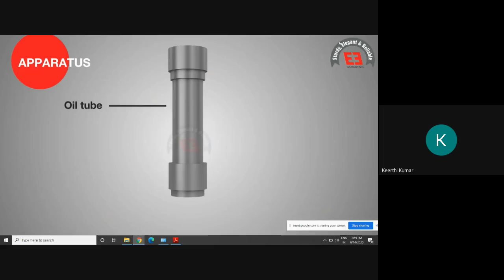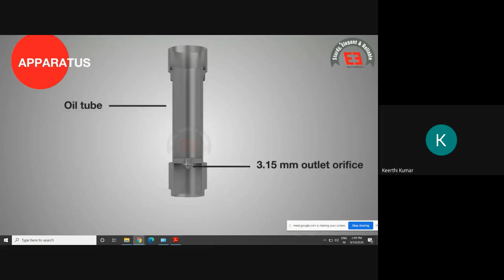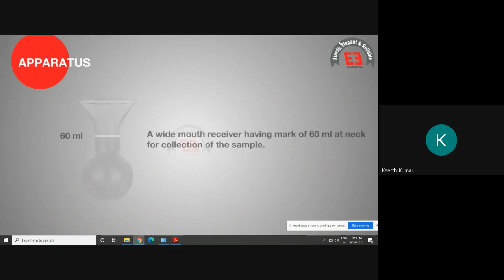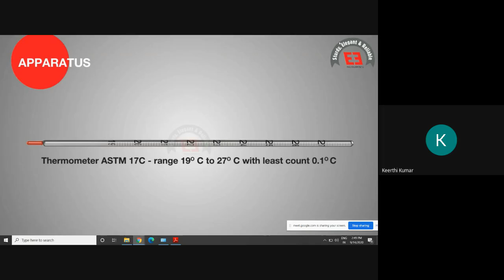Apparatus. Saybolt Furol test apparatus consists of an oil tube with overflow rim at the top. The oil tube is having an outlet orifice of 3.15 mm internal diameter and a stopper cork at the bottom. The oil tube is fixed in a thermostatically controlled water bath with stirring device. The lid of the water bath is having a heater and cooling coil to bring down the temperature of the bath media. The bath is placed on a tripod stand with leveling arrangements. A wide mouth receiver having a mark of 60 ml at the neck for collection of the sample. Thermometer ASTM 17C, range 19 degrees Celsius to 27 degrees Celsius with least count of 0.1 degrees Celsius. Thermometer ASTM 19C, range 49 degrees Celsius to 57 degrees Celsius with least count of 0.1 degrees Celsius. A stopwatch to read with an accuracy of 0.1 second.